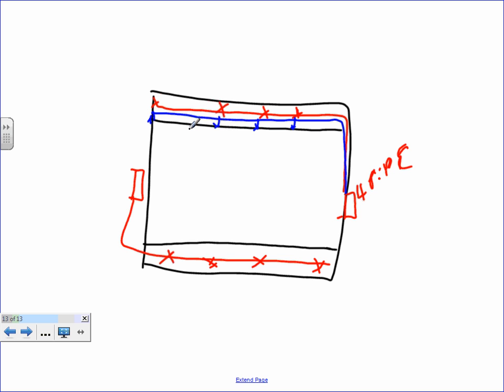What we have done in the past is we put at the top the 30 by 30, and at the bottom we say cut it by half, because we don't know the air exchange, just as a rule of thumb. So we place the bottom ones at 7.5 on center. All these smoke detectors under the raised floor at 7.5. I'm sorry, 15 on center. 15 on center. So that we call it a day, unless we know otherwise. Which is fine if you don't know.